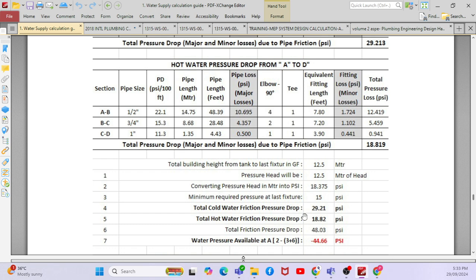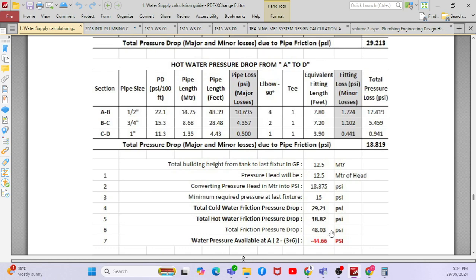When you add all the pressure drops, the total cold water friction pressure drop comes to 48 PSI. This can also be expressed in feet, meters, or bar — the values are equivalent, only the units differ. To convert PSI to bar: 14.5 PSI equals one bar, so 48 divided by approximately 14.5 gives roughly 3.3 bar. So that is the way to calculate your pump head for the water booster pump — it is quite straightforward.